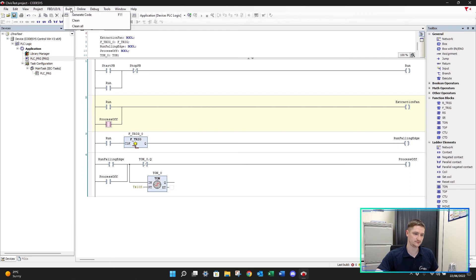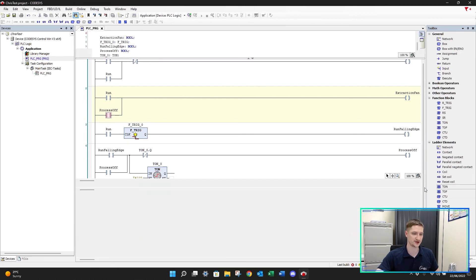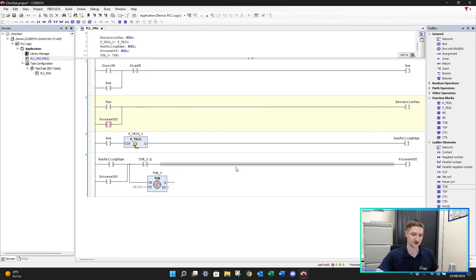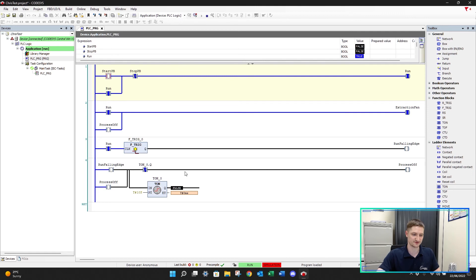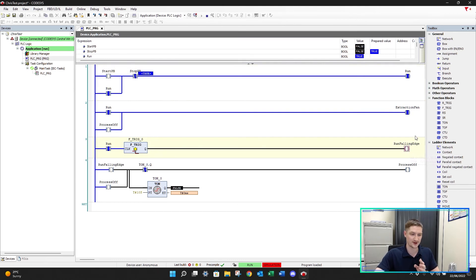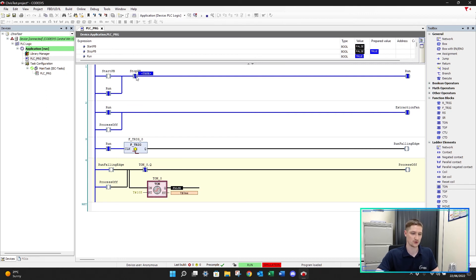Let's save our work, build and generate code - no errors, no warnings. Let's go online, click simulation, log in and download this program, then start the PLC. I'll double click my start pushbutton and Control F7. Our run signal is latched on and our extraction fan is on. None of the timer logic is running yet because our run signal hasn't turned off. I'll double click my stop pushbutton and Control F7.